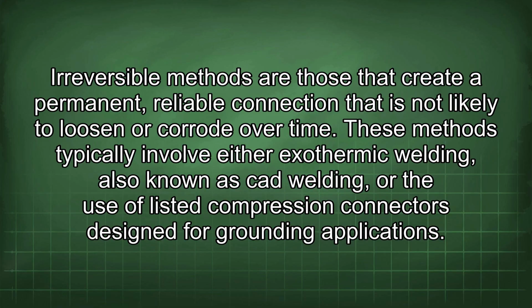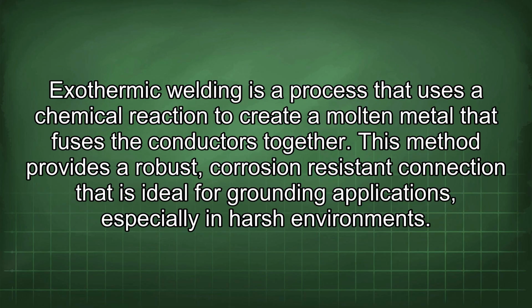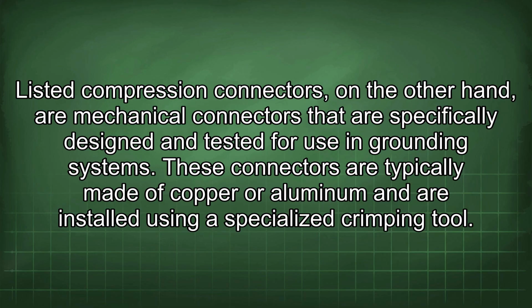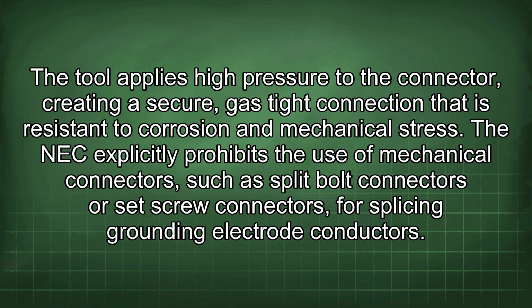for grounding applications. Exothermic welding is a process that uses a chemical reaction to create a molten metal that fuses the conductors together. This method provides a robust, corrosion-resistant connection that is ideal for grounding applications, especially in harsh environments. Listed compression connectors, on the other hand, are mechanical connectors that are specifically designed and tested for use in grounding systems. These connectors are typically made of copper or aluminum and are installed using a specialized crimping tool.